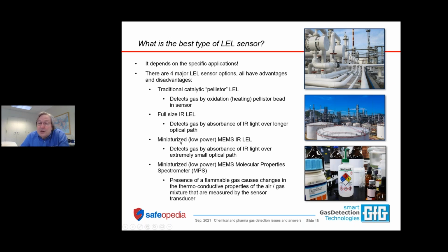The miniaturized low power IR LEL sensors, the ones they put on a chip, these MEMS sensors, the benefit is that they take very, very little power to operate. The bad news is they are primarily designed for the detection of methane, and they are often not very accurate for other types of combustible gases.